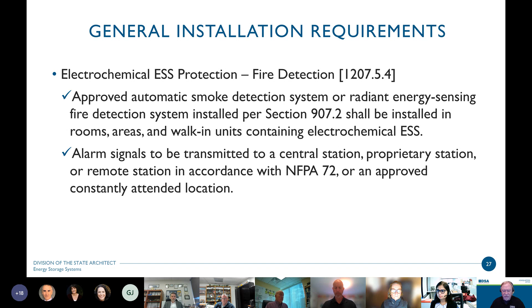Fire detection required. An approved smoke detection system or radiant energy sensing fire detection system needs to be installed per 907.2 of the fire code. These will be installed to cover those areas in the walk-in units where we have this electrochemical process occurring. And these systems need to be able to transmit alarm signals to a central station, proprietary station or remote station in accordance with NFPA 72, or an approved constantly attended location, similar to what we already do for fire alarm systems on our school campuses.